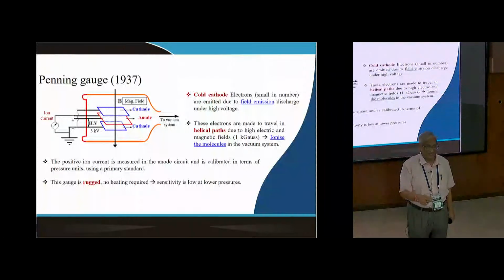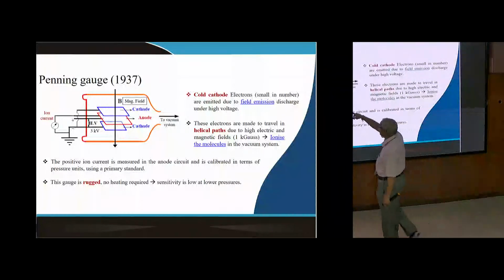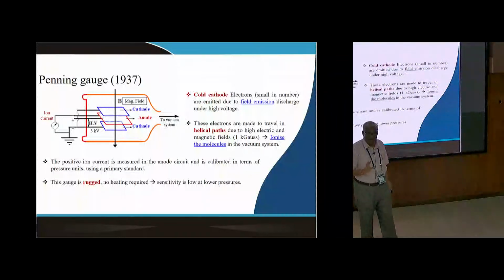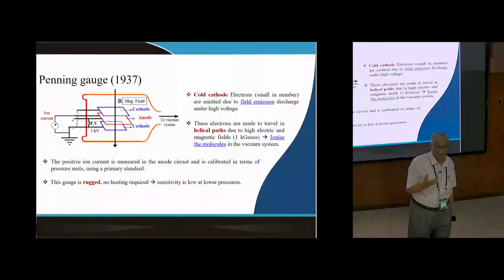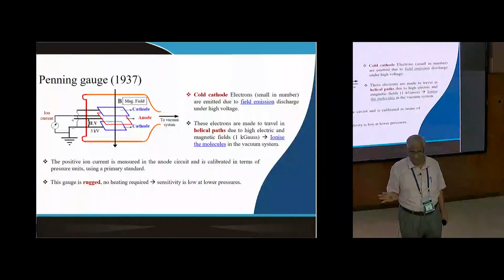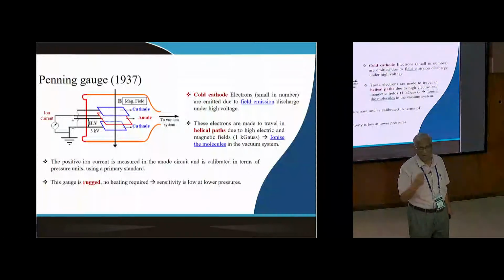But how do you ionize them? First, these are only a few electrons. They have to be amplified and accelerated so that they have enough energy to ionize the atoms and create a plasma. How do you do that? You can accelerate by electric fields, by high voltage, 3 kilovolts. In a Penning gauge you have 3 kilovolts, and you have an applied magnetic field. The magnetic field does not do any acceleration. It will only confine the electrons. Charged particles will not cross the magnetic flux lines, so they keep on rotating.